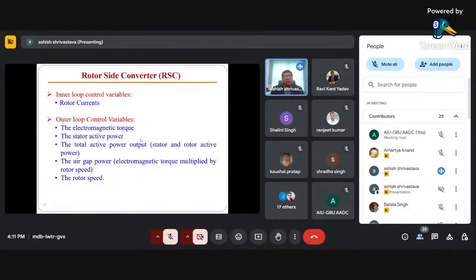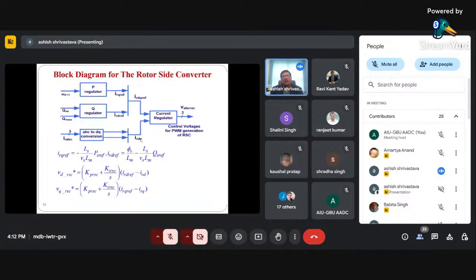There would be an inner loop control, which is rotor currents, and the outer loop control variable will be electromagnetic torque, stator power, total active power, whether stator or rotor active power, then air gap power, which is the electromagnetic torque multiplied by rotor angular speed, P equals omega times torque. So you can decide two kinds of loop for the RSC. One is the inner loop, where rotor currents are the control variable, and in the outer loop, torque, active power, reactive power, air gap power and rotor speed can be taken care of. This is how the control can be decided.